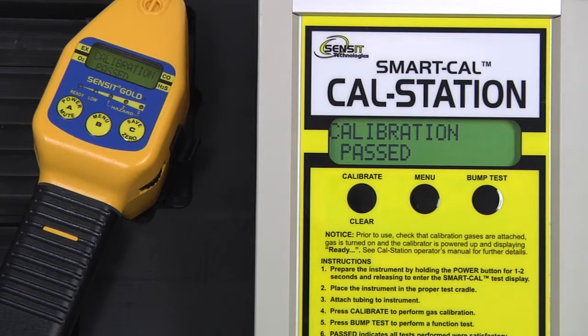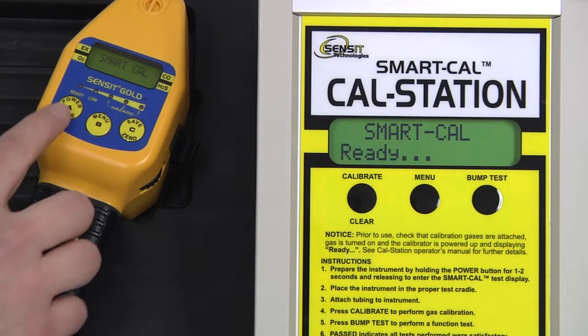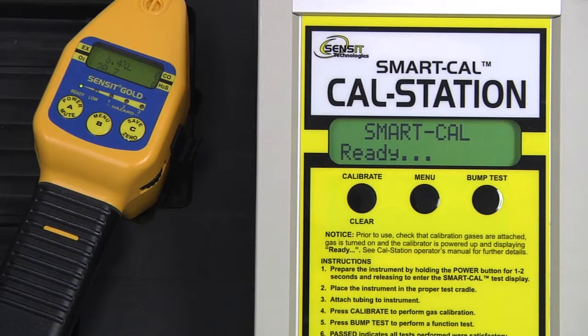Calibration is passed. We can exit out of the calibration mode on the cal station by pressing and releasing the calibrate or clear button, and exit out of the SMART-CAL mode on the instrument by pressing and releasing the A button, and finally removing our instrument hose from the end of the gooseneck.